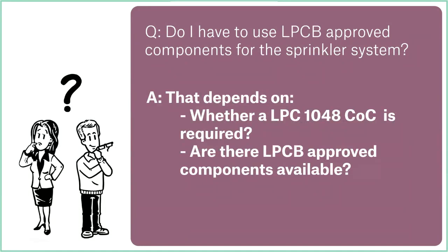approved equipment. If you just want the sprinkler system to be installed to the British standard, then there's no requirement to use any particular approved components. The British code standard will not refer to particular manufacturers or particular approval bodies. They are completely independent. All they will say is that the equipment needs to be appropriate or fit for purpose. You can't just use any old thing lying around. It has to be good quality, decent equipment. But there's no requirement to use any particular approved equipment.